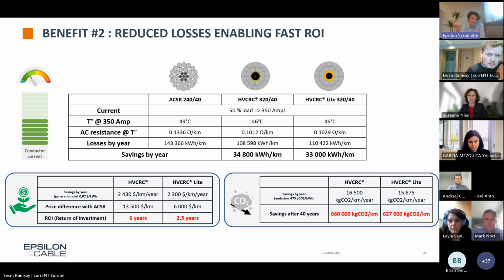There's a second benefit in using those advanced conductors with composite core. Though they are more expensive than standard conductors with a steel core, they have a very short return on investment. How come? Thanks to the reduction in electrical line losses during operation. These conductors - you have sketches on the left-hand side showing a standard conductor with steel core, and on the right-hand side composite core with trapezoidal aluminum wire around them - have higher aluminum content by about 30%, which makes it possible to reduce line losses to the same extent.